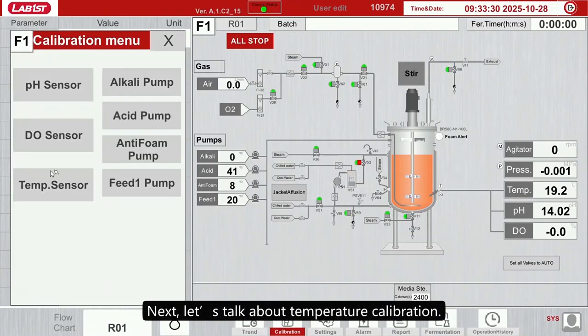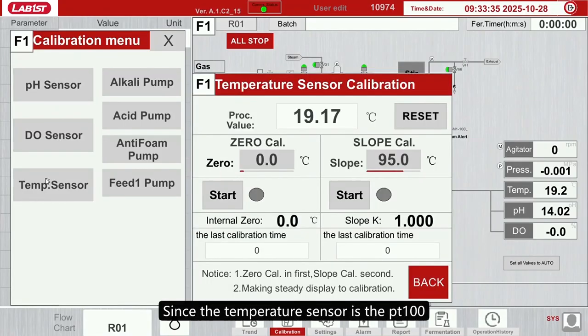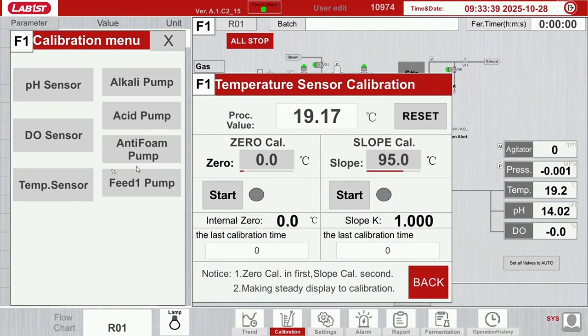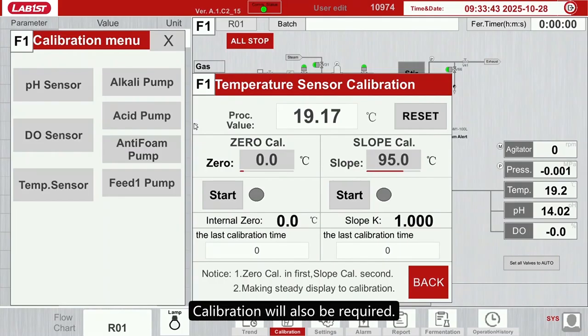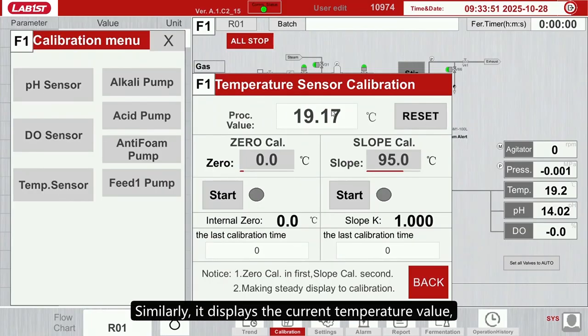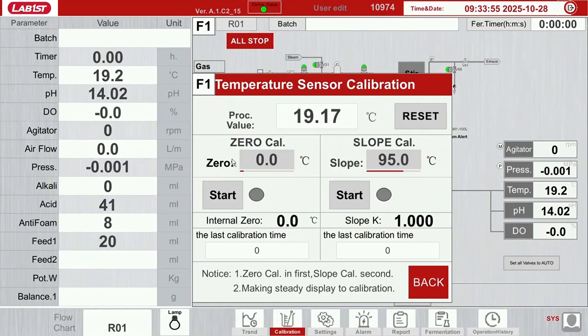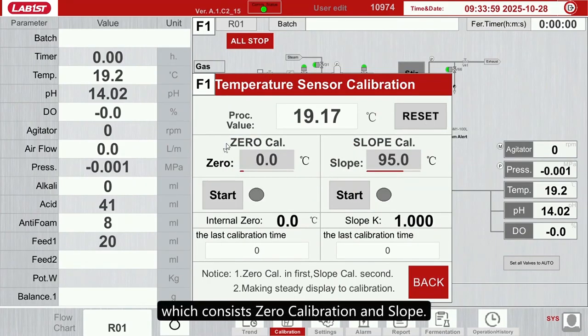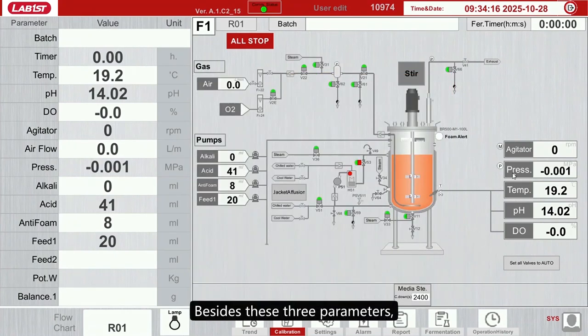Next, let's talk about temperature calibration. Since the temperature sensor is a Pt100, it is quite stable. Generally, it doesn't require calibration. However, based on customer needs, calibration will also be required. It can be done here. Similarly, it displays the current temperature value, as well as a reset option. It also has an internal calibration method, which consists of 0 calibration and slope. And it shows an internal display, as well as the last calibration time, which is similar to pH and DO. Besides these 3 parameters, the agitator can also be calibrated, but this function is not available to customers. If needed, please contact sales.